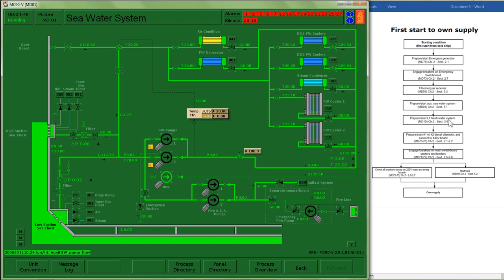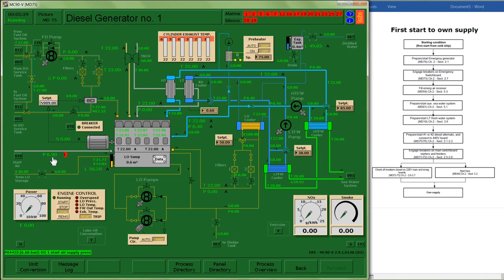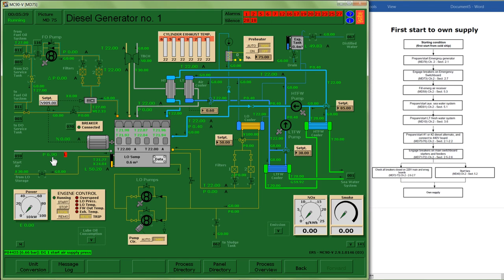Maybe about 50% sounds good. My pressure is still building. It'll need to be at least 15 in order for me to start. If I follow through my lube oil system I'm going to have a pump. I'm going to turn this on and I'll turn it into auto. So it'll continue to build pressure. I don't have any flow in my system. I'll need to create a pathway through a filter and that will allow flow through my lube oil system.